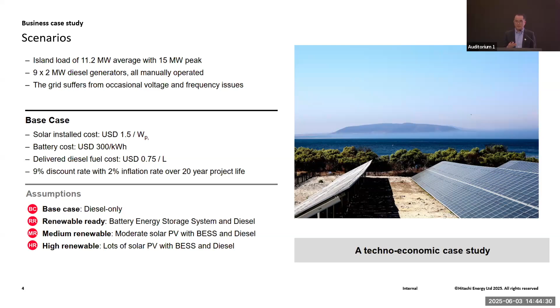We are looking into 4 different scenarios. The first scenario is the island and remote community running on a diesel-only basis. We assume this island has roughly 11 megawatts installed consumption, with peak going up to 15. Each genset can provide 2 megawatts of power supply. In daily operation, 8 gensets have to be running, with 1 acting as a spinning reserve - a spare genset that's on but standby.